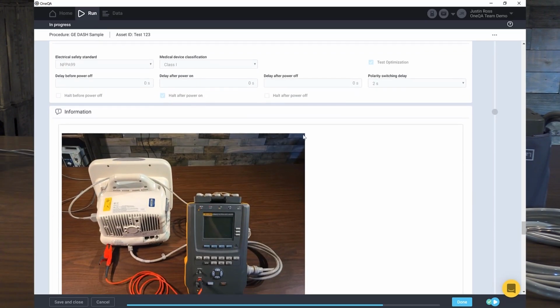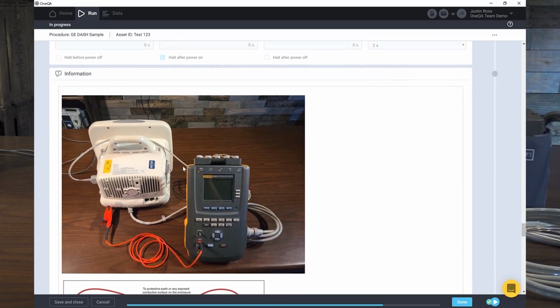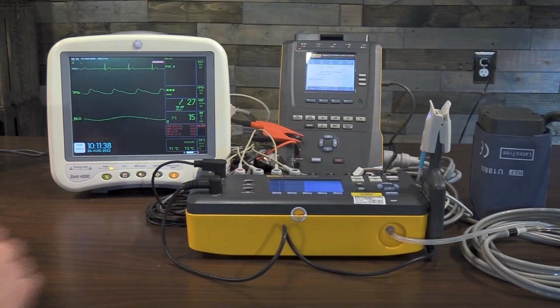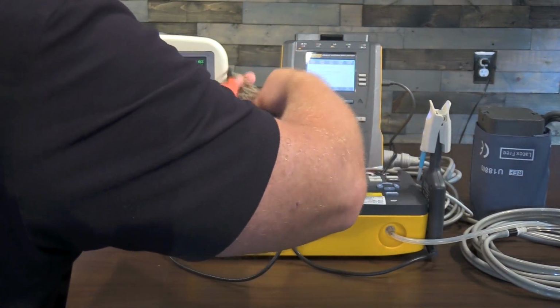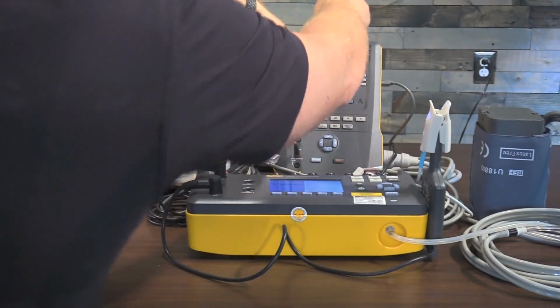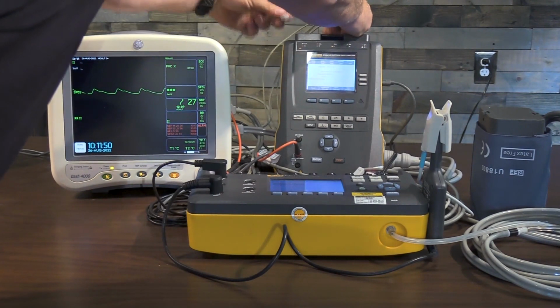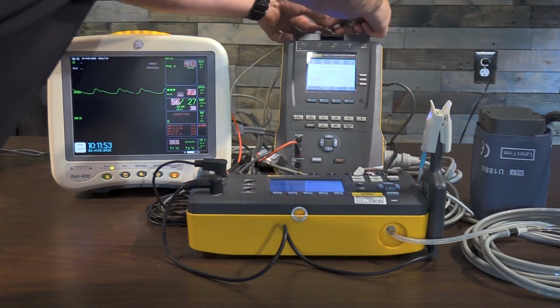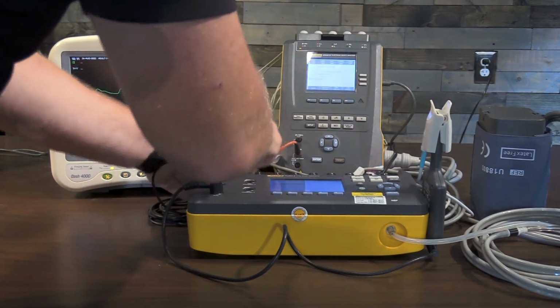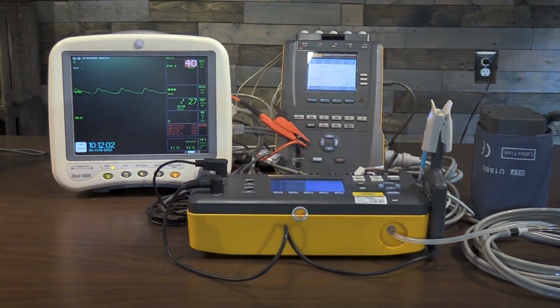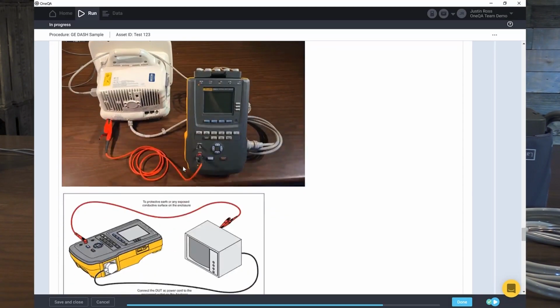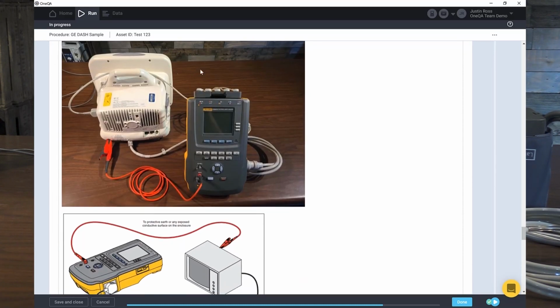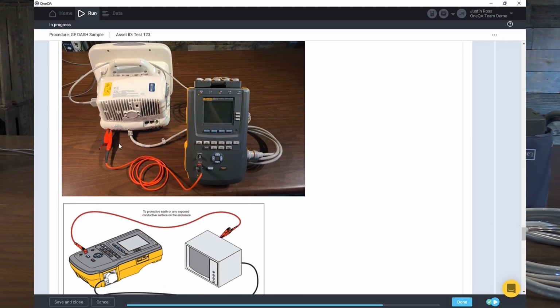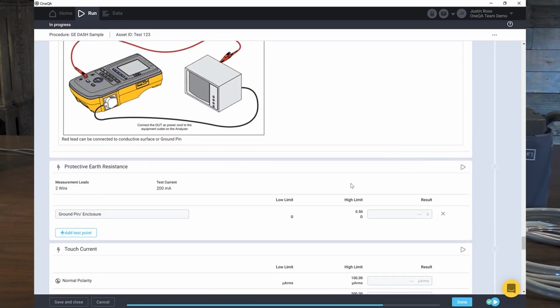In our electrical safety test, here's what we're going to do. We're going to follow an NFPA 99, and here is the setup for it. So let me go ahead and we'll move my ECG leads up to my safety analyzer. All right. Now I'm going to leave this here for a second because I have to zero out my leads. So there's my setup. So I know exactly how to set up for my test, my ECG leads, and I'm going to take my red alligator clip back to here. But I know from running this a few times, I have to zero out my leads first.